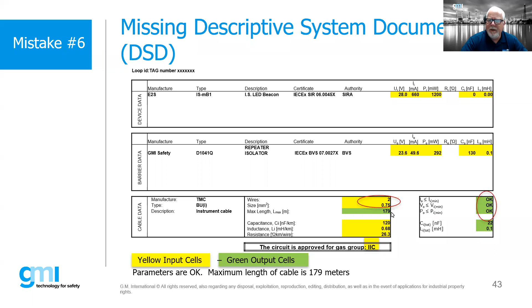We've also taken the information from our cable manufacturer. What this tells us is these numbers here. It's telling us that everything is okay from a safety standpoint, but the big thing here is the maximum length of cable is 179 meters based upon this application.